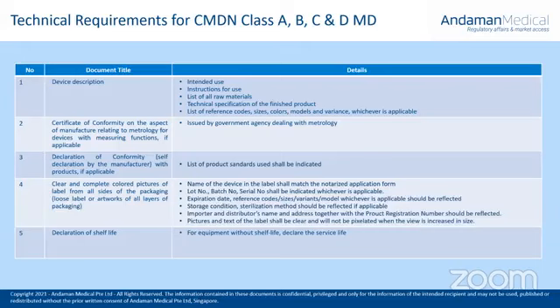Next is the name and address of the importer and distributor together with the product registration number. It's mandatory in the Philippines to reflect the name and address of the manufacturer, of the importer and the distributor, alongside the product approval number, the CMDN or the CMDR number. The pictures of the label shall be clear and not pixelated when the view is increased in size. Also, if your label has a CE marking, you need to submit a valid certificate supporting the placement of the CE mark. For imported medical devices, if the local company makes its own brand, a declaration from the manufacturer allowing the use of the brand name and IPO approval of the said brand shall also be submitted.